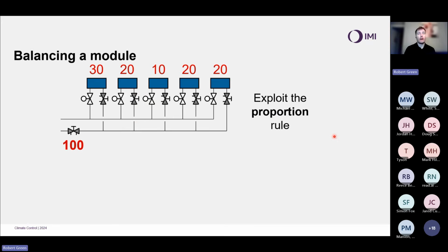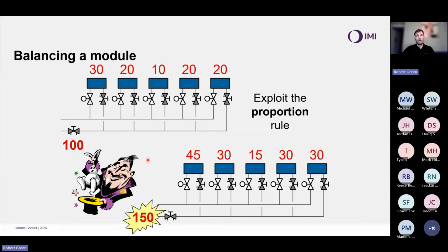Let's take an example here where we have 100 flow units, or 100% of flow. And we have a split of 30, 20, 10, 20, and 20. If I wish to exploit the proportional rule, it states that any change I make upstream affects all units downstream in the same proportion. So if I adjust this valve to 150, we can see magically a 50% increase in flow in each of these 5 units. 30 to 45, 20 to 30, 10 to 15, 20 to 30, and 20 to 30.